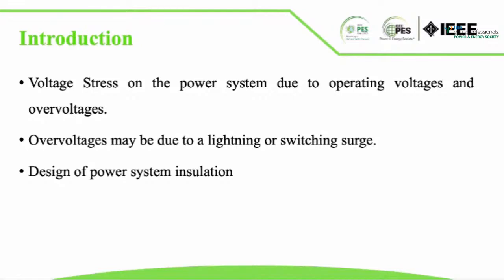Thus, operating voltage determines the dimensions of the insulation which forms a part of the generation, transmission and distribution equipment. The voltage stress on the power system arises due to different overvoltages also. They may be either external or internal. External overvoltages are those associated with lightning discharges, and internal overvoltages may be due to changes in the operating conditions like switching operations, fluctuations in load or generation, or also due to faults that occur in the power system. Thus, the design of system insulation is a major area which we concentrate on.